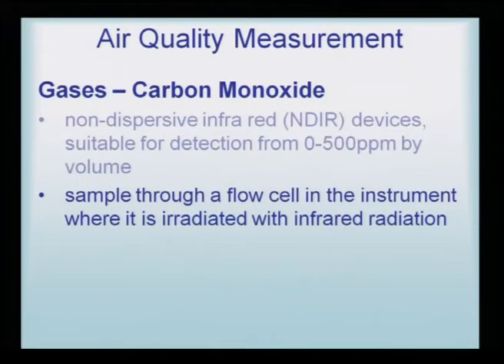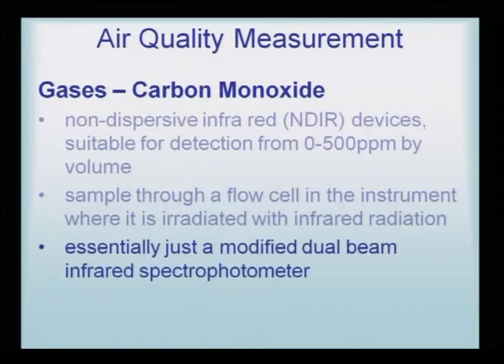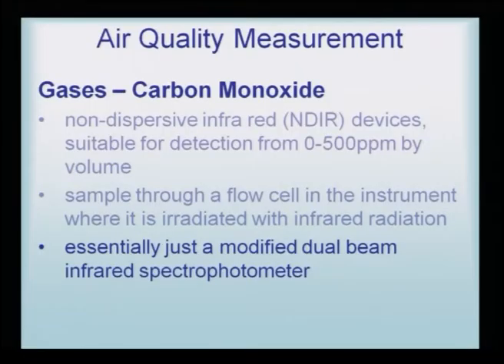Carbon monoxide gas is particularly infrared light sensitive, whereas SOx and NOx were UV sensitive. Essentially, a modified dual beam infrared spectrophotometer can do the needful. So if we have a carbon monoxide sample, we can analyze it on a double beam infrared spectrophotometer.